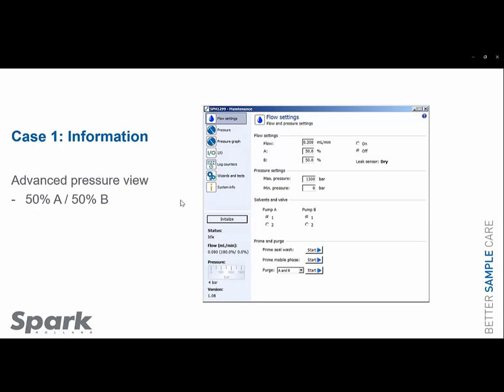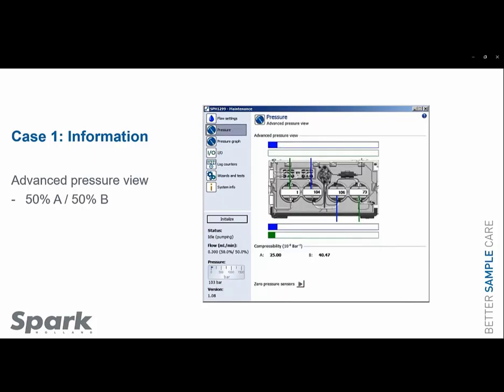Secondly, we will run the pump for 50-50% AB. Running 50-50%, we observe what the pressure is doing. We see that pump A cannot aspirate anything. We see pressure building up in the secondary pump head, but the pressure on the secondary pump heads will only be generated by pump number B. Pump A doesn't do anything. It's not aspirating anything. As you can see, the pump is also pumping up with an error message, compressibility error 778, which is based on the compressibility error on pump number A.